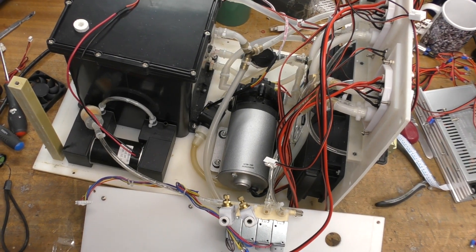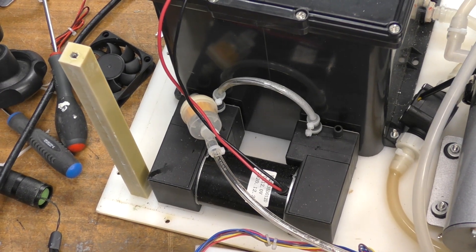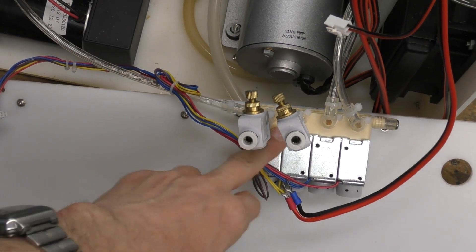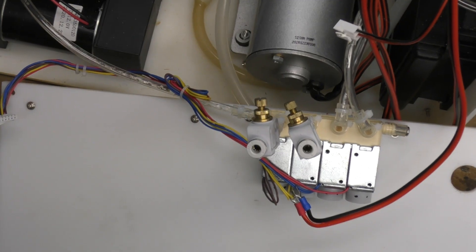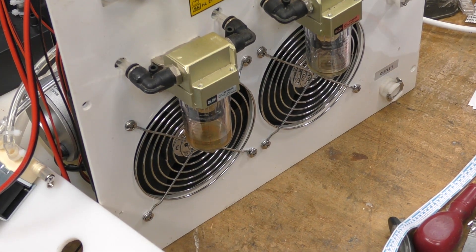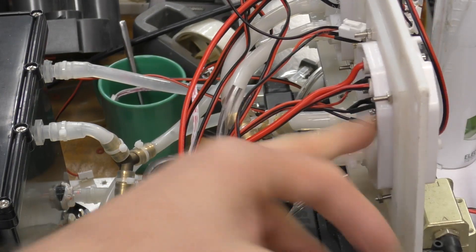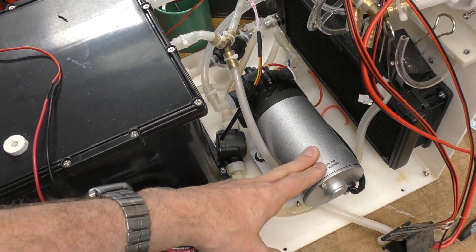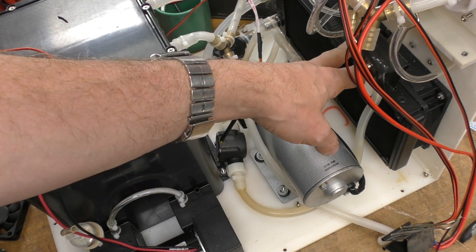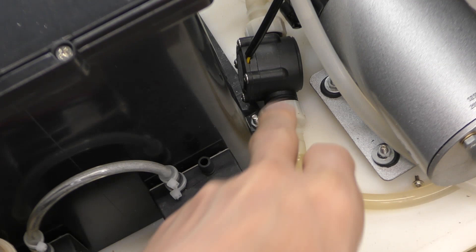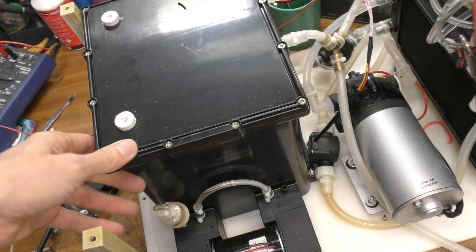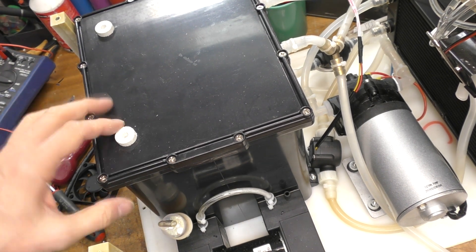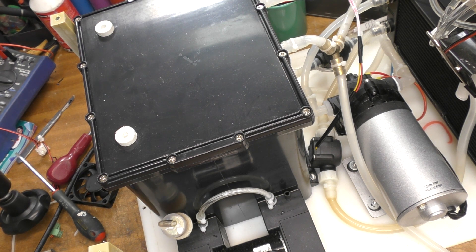Taking that top deck off, we've got a few mechanical parts down here. There's this suction pump that goes into a bank of four valves, going to a manifold with one pipe to each of the liquid traps on the back. I don't really want to think too much about what that liquid is in there, but that's whatever's getting sucked out from the laser head. Down here we've got this pretty substantial pump for the cooling liquid. There's a radiator on the back with two fans. This is obviously potentially getting rid of quite a lot of heat. There's a filter, a flow sensor so it knows the coolant's actually flowing, and this is a big reservoir tank still fairly full - you can hear it sloshing. I don't know if this is pure water or some sort of other coolant.